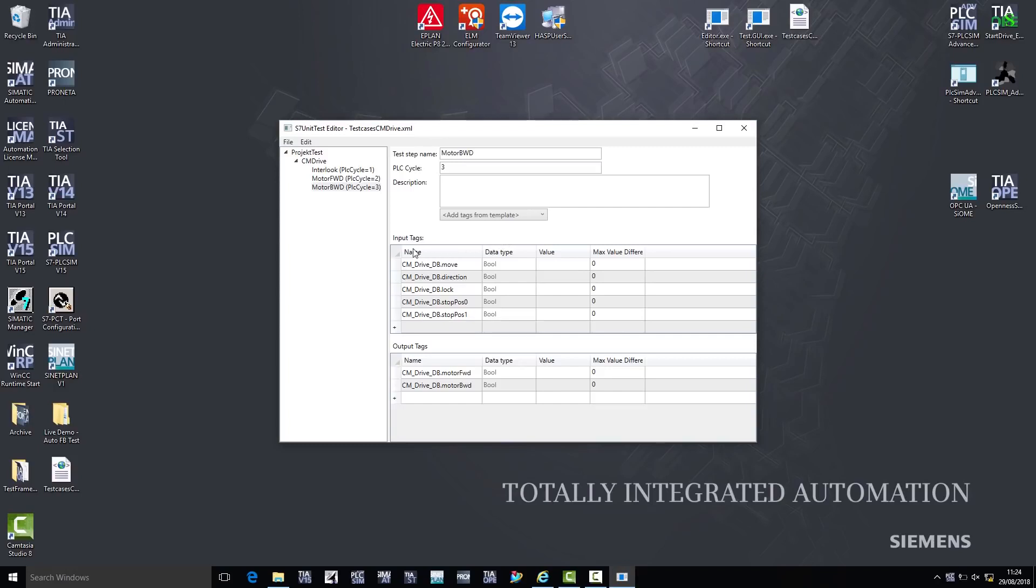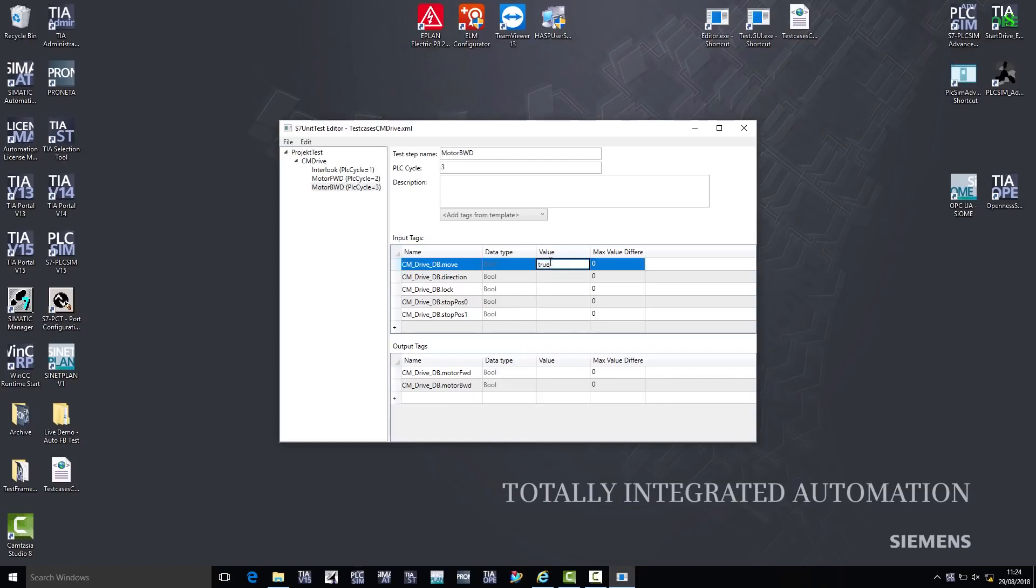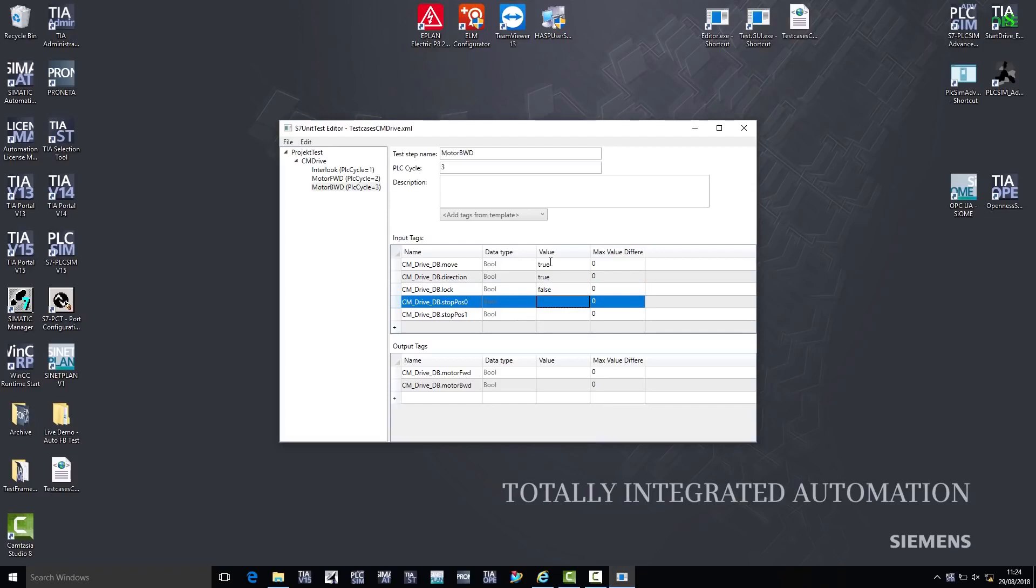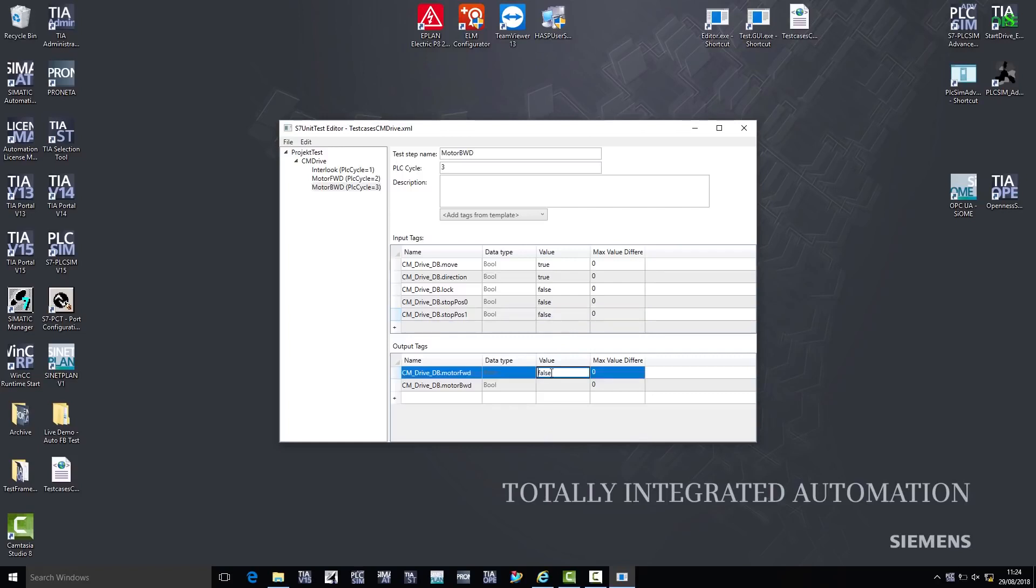I now determine the input values for my test case. This means that the command for the drive move is set to 1, and the direction is also set to 1 for this test. For this input parameter, I expect a return value of 1 for the motor backward, if the function block works correctly.